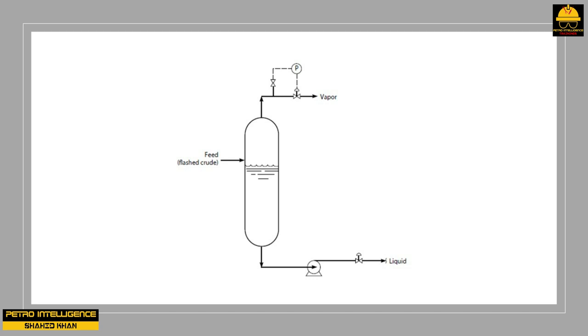At a refinery, operators had to start up a new flashed crude oil pump that had never been run before. They reported that the pump always cavitated on startup. They raised the liquid level in the drum to within a few inches of the inlet nozzle — a higher level would cause entrainment of black crude oil into the vapor outlet. They started the motor and very slowly opened the discharge valve, but regardless of their efforts, the pump cavitated so badly it could not be put in service.